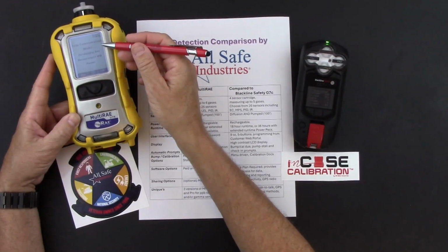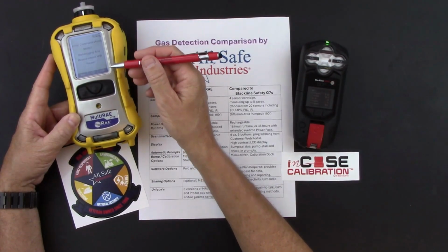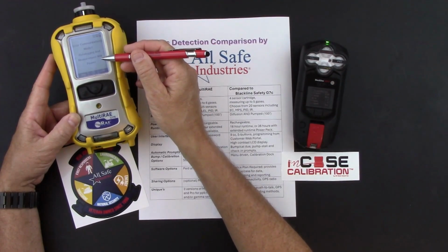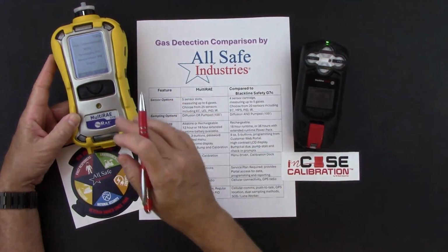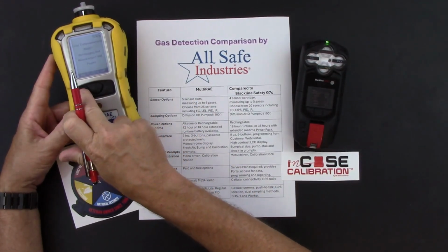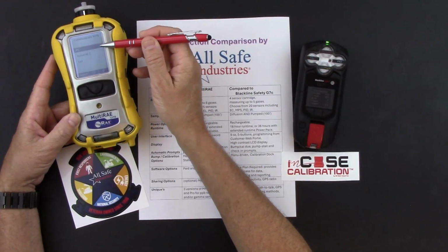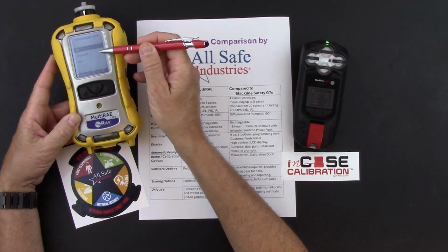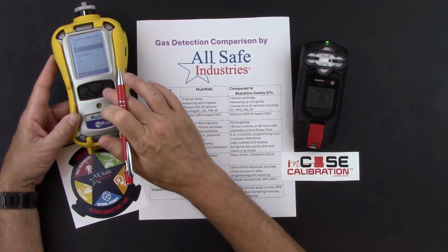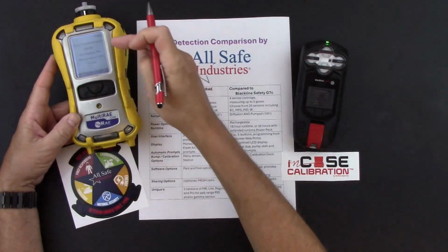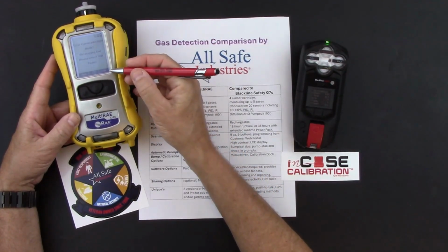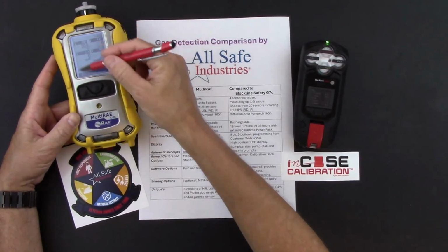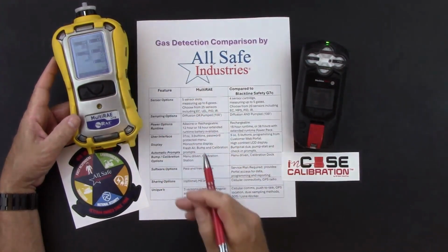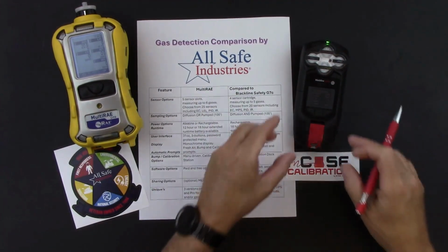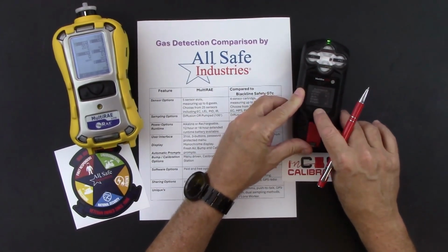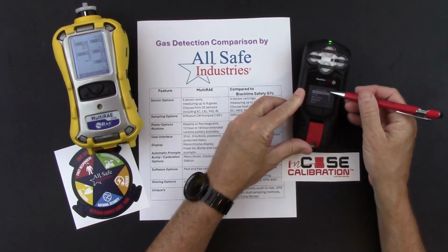And then my last page is my Enter Communications Mode screen. It reminds me that my data logging and my measurement will pause if I enter this communication mode. This is a maintenance screen. So if I say yes to this, you can see that I can communicate with a personal computer, with an RAE 2 calibration station, or I can drop down to exit, and then I go back to that Enter Communication Mode screen. If I advance the screen one more time, I come back to my main reading screen with my real-time readings of my 5 different sensors. On the G7c, if I press the OK button 2 times, you'll get into the main menus.